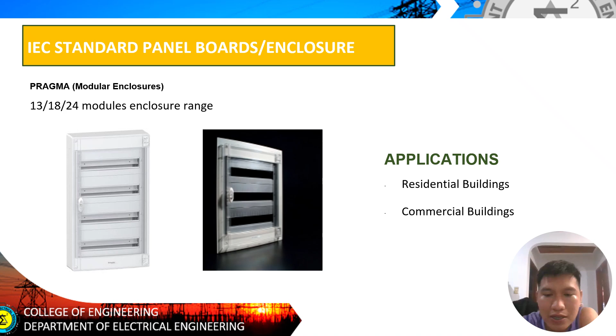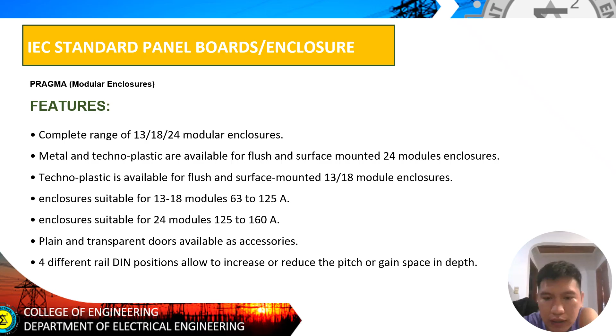Yan yung feature naman nito. Complete range, metal and technoplastic, enclosure suitable for 13-18 module, 63 to 125 ampere. Enclosure suitable for 24 modules naman is 125 to 160 ampere. Plain and transparent doors available as accessories. 4 different rail DIN position allowed to increase or reduce the pitch or gain space in depth.